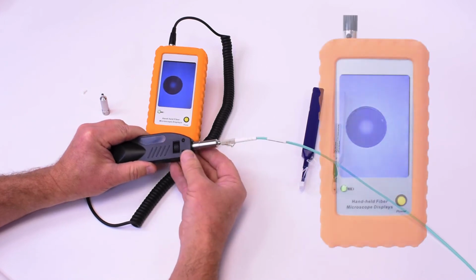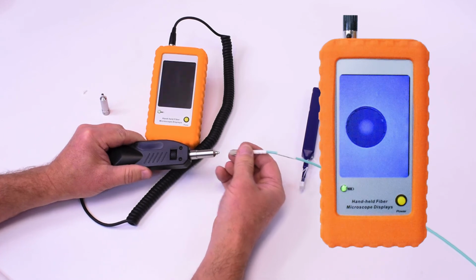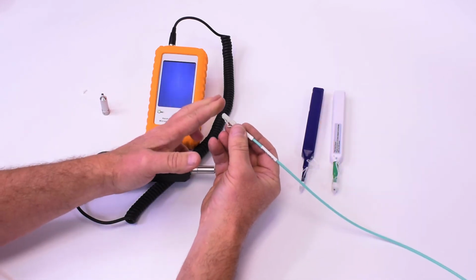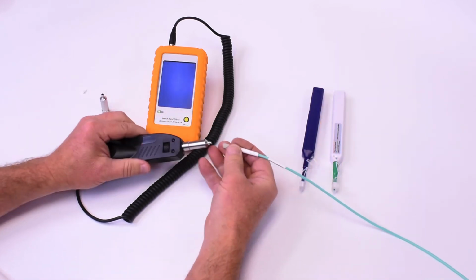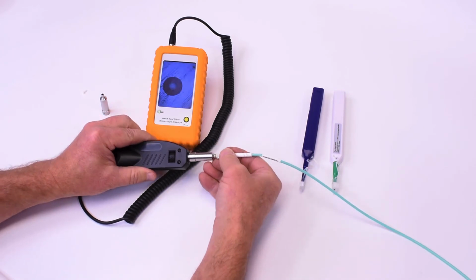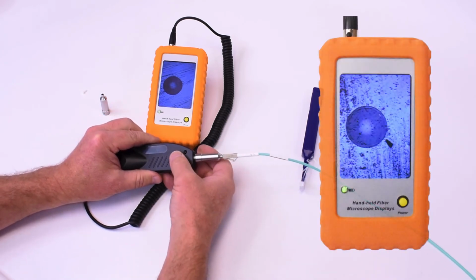A clean connector end face will have an image that does not show dust, lines, or other contaminant. For example, touching the connector ferrule will result in contamination. The screen will show additional lines and marks.